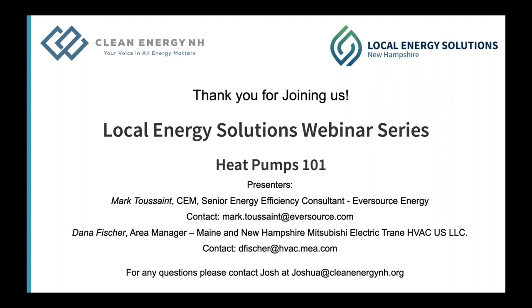So there are different kinds of concerns about heat pumps and the amount of electricity that they may or may not use at different times. And it's true that in order to stay ready, heat pumps need to make sure that the oil in their compressors is not cold, so that it can turn on and operate at a given time. So when it's very cold outside, heat pumps will continue to use 80, 120 watts of power through the windings in their compressor in order to maintain the compressor oil temperature. That's where we're really getting to some super nitty gritty. We're talking about the equivalent of a couple dollars worth of electricity over the course of a month.